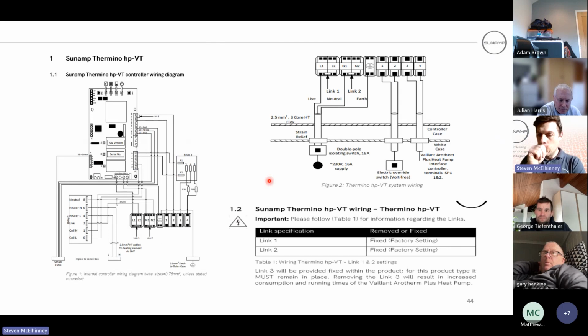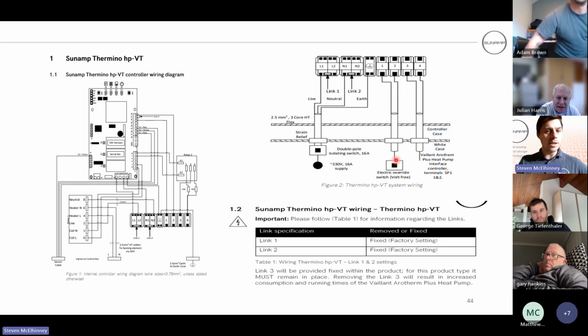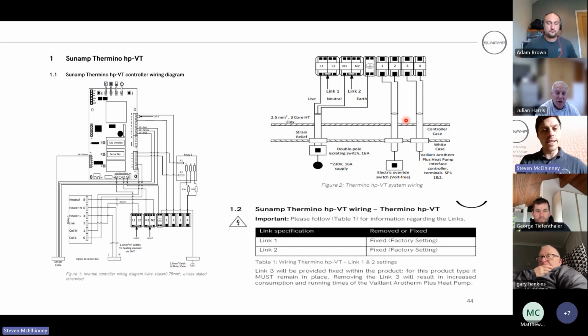So the Vaillant, standard Vaillant, as I call it, again, you've got your resistor set up here. So again, 2 fixed values. But we've got an electric override switch for the Vaillant. We've got your control circuit. So you run your 2-core back to SP1, 1 and 2, back to your heat pump interface. But you've also got an override switch if there's a heat pump failure for any reason. So the customer's got a bit more functionality. Again, 2 separate 2 cores in case there's any interference with the two sides of things.